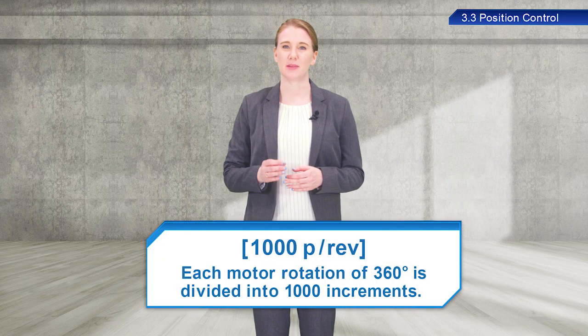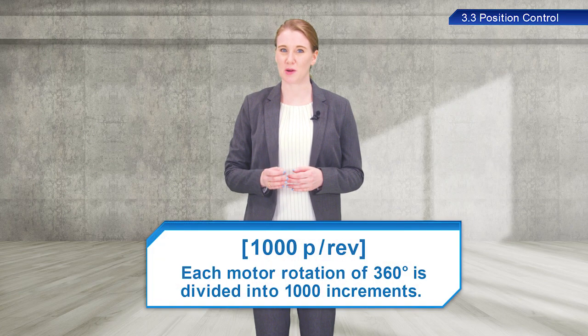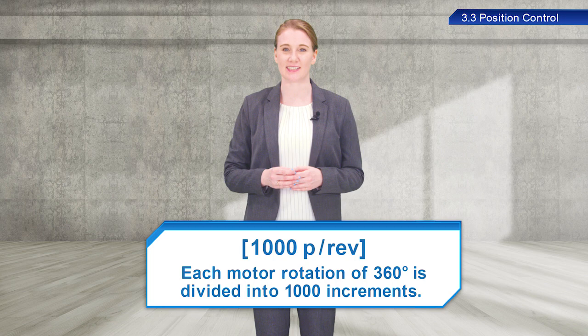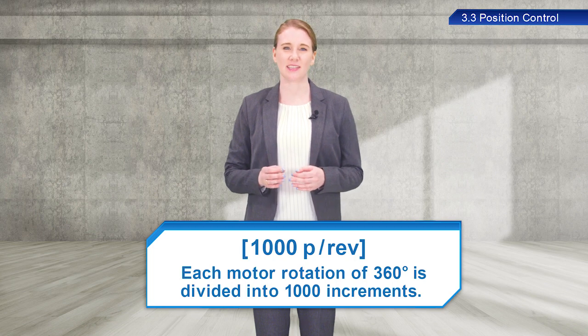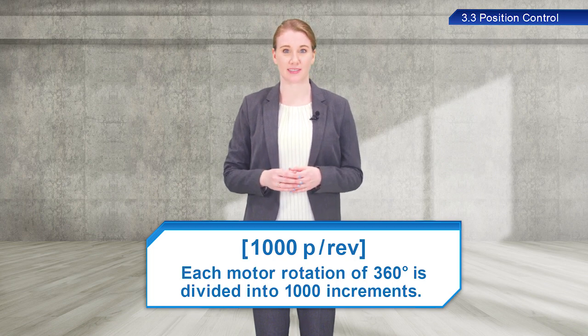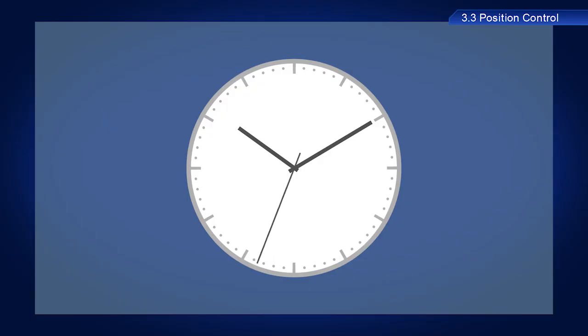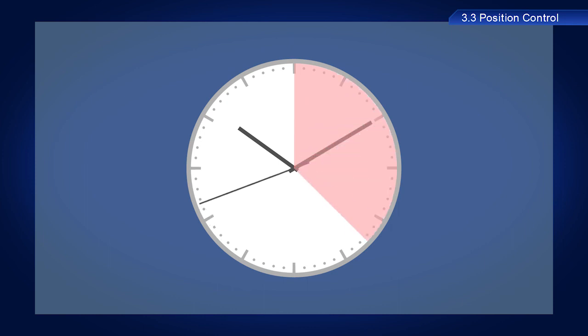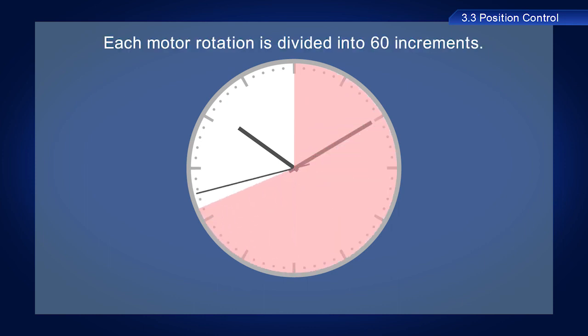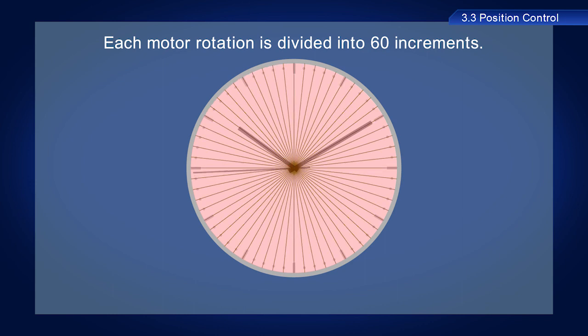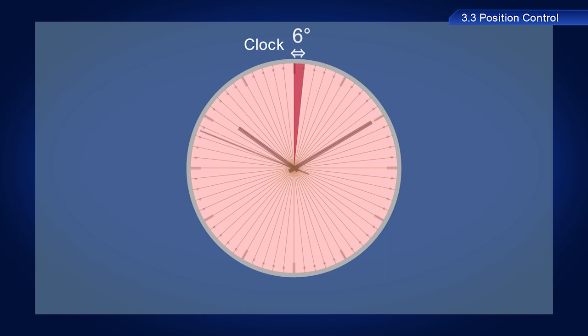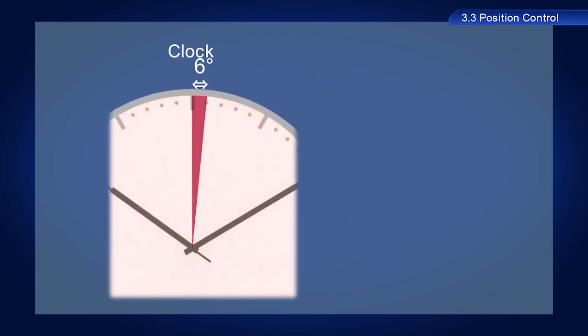1000 pulses per rev means that each motor rotation of 360 degrees is divided into 1000 increments. Servo amplifiers output a signal once every pulse. As such, in this example, each pulse causes 0.36 degree of movement. In comparison to a clock, because the second hand of the clock rotates one rotation in 60 seconds, 360 degrees is divided into 60 increments. As such, the second hand moves 6 degrees for each tick.